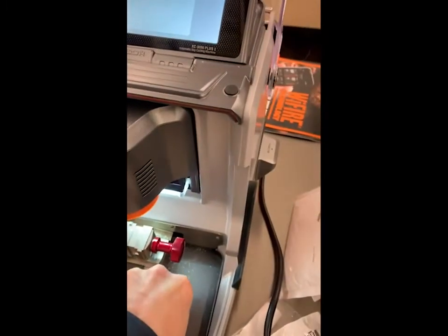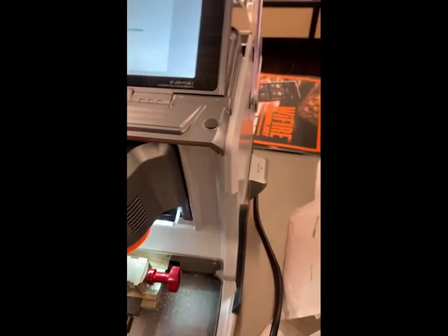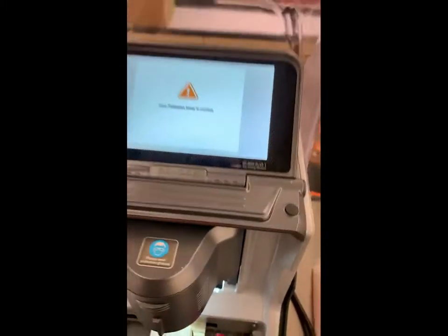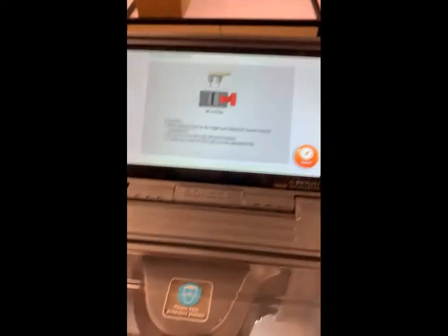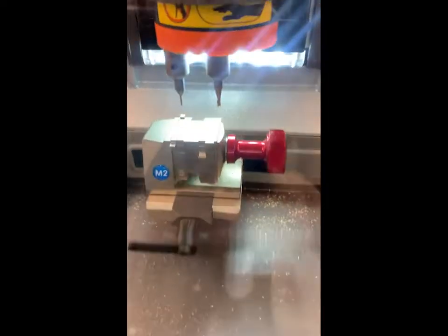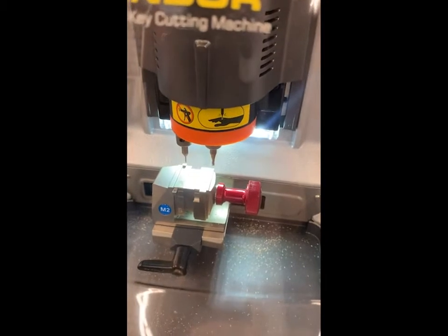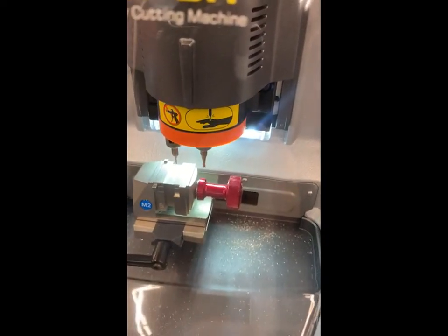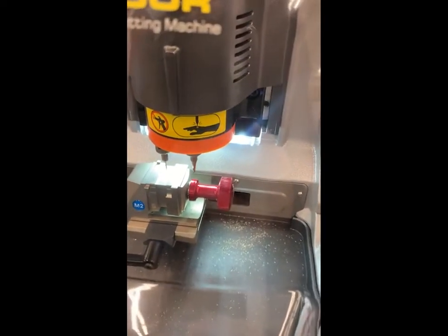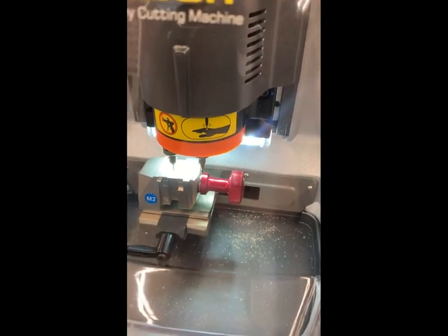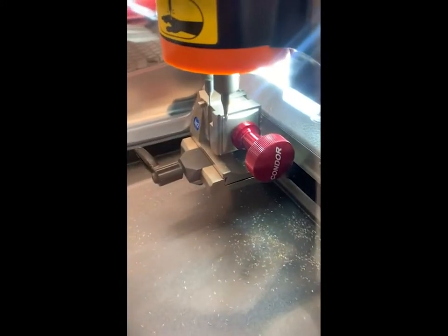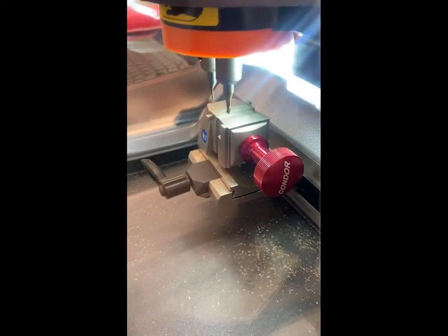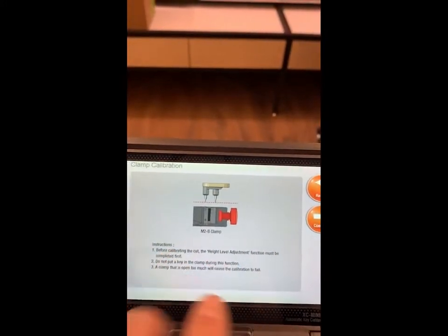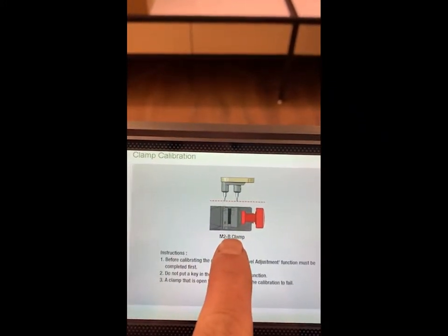Here we go. You always want to make sure this is nice and clean. It says not to have it open too much. Here we go. We're going to continue, and this is going to check side A. So it's checking the lug. Now it's actually checking the points on the jaw itself. It's just a little harder to see because that light is so bright. All right. And now what I want you to see, nothing on the screen changes except that letter. Now it wants you to go to B.